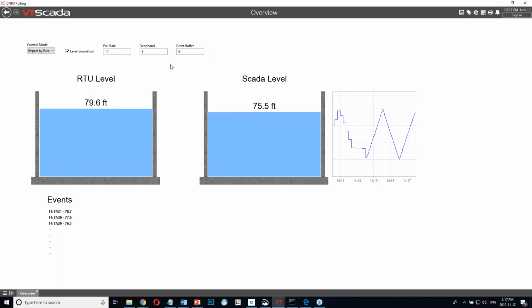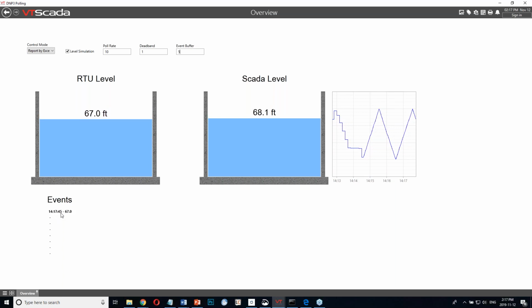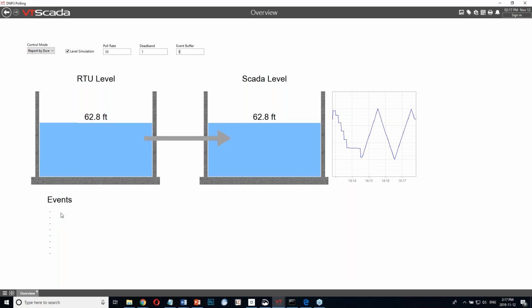But what happens here is you might configure the level of your lift station. Yeah, it's changing all the time. You don't critically need that. Maybe once you've got 10 pieces of data for it, or you've had events in there for at least 2 minutes, or whatever metrics you want to use, you should just update the SCADA system so it's relatively up to date.